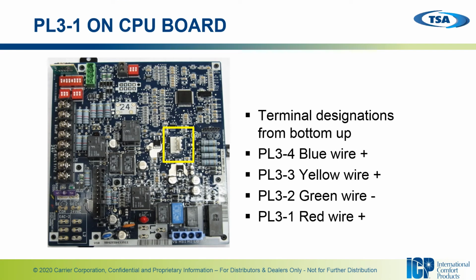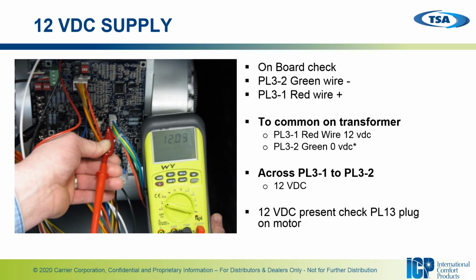Okay, so troubleshooting from the board end of the blower control system. You're going to have terminal designations on the control board in plug number 3. Okay, we'll start from the bottom up. So plug 3-1 should be a red wire. Plug 3-2 should be a green wire. Plug 3-3 should be a yellow wire. Plug 3-4 should be a blue wire.